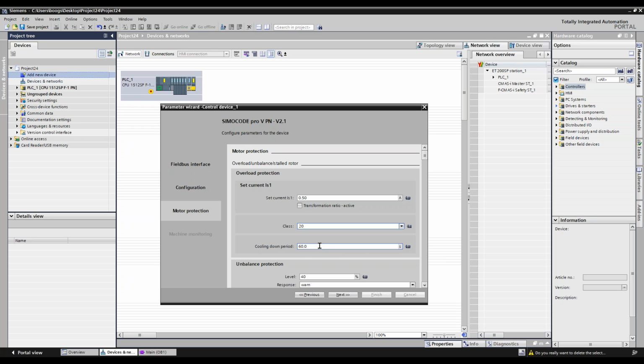We can put in here, let it cool down and let it go for 600 seconds if I wanted to. Notice that I can go in here and hold on this and go down the cooling down period. We can make it up to 65,530 or 6,553.5 seconds. So, the default setting is 300 seconds. So it could be a long time for that.